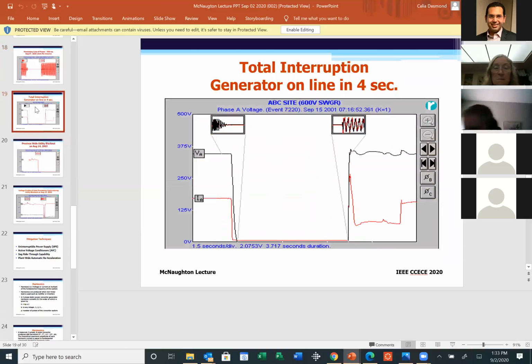I thought I'd share with you this one. Look at the black line, the voltage, how it went all the way from the normal value to zero, and then it came up. If you look at the black line, this window was 4 seconds. The reason is 4 seconds: that's how long it takes for the emergency generator to start and assume the load. So during the 4 second window, this site was in total blackout, except, of course, for the critical equipment, where the UPS batteries support their computers. And once the generator is up and running, they support the critical equipment via the UPS. So in this case, everything worked, as we call it, as designed. Next slide, please.